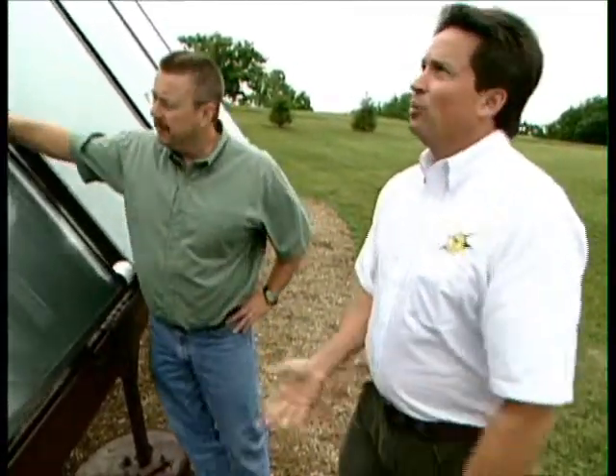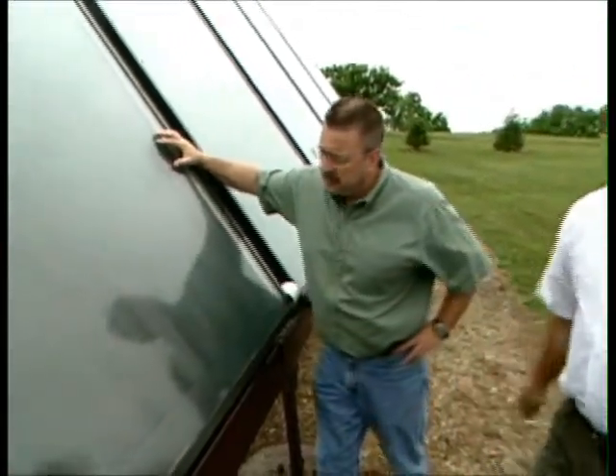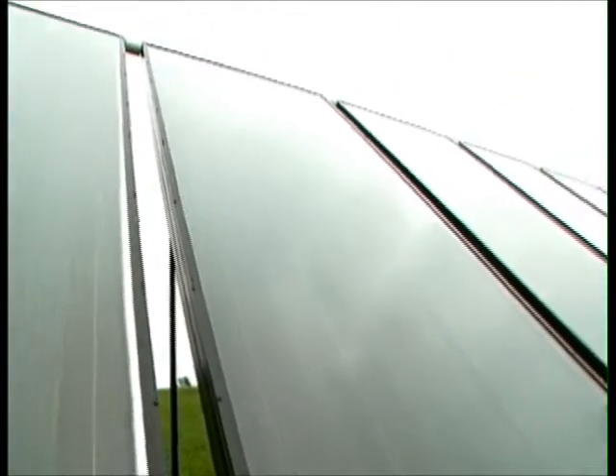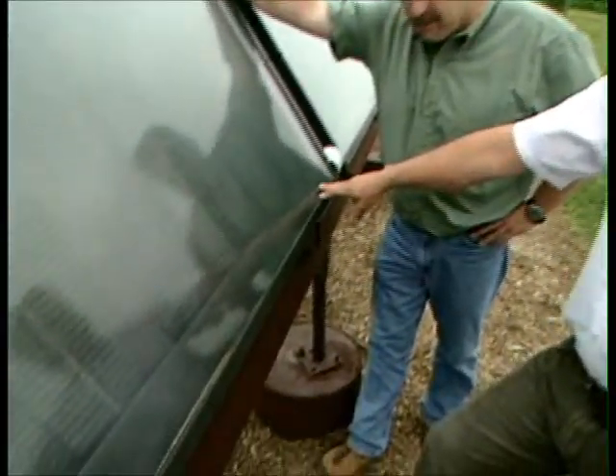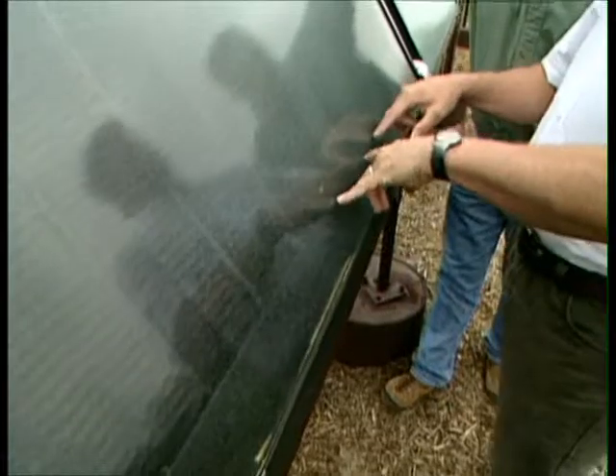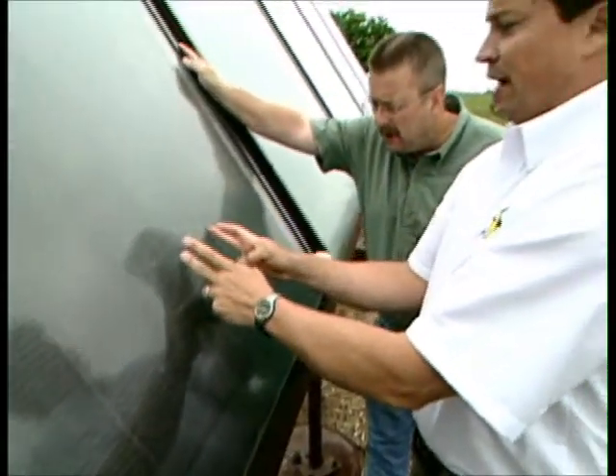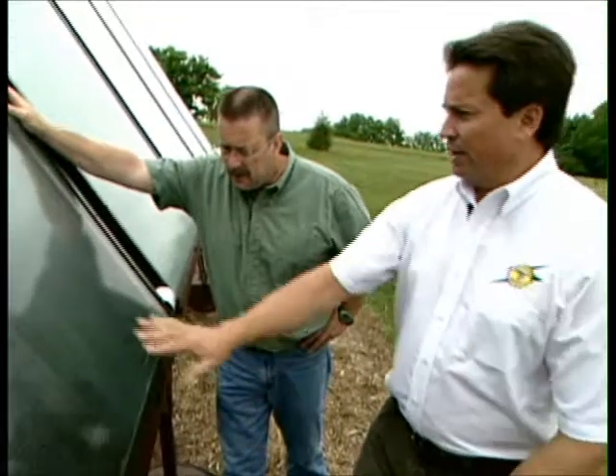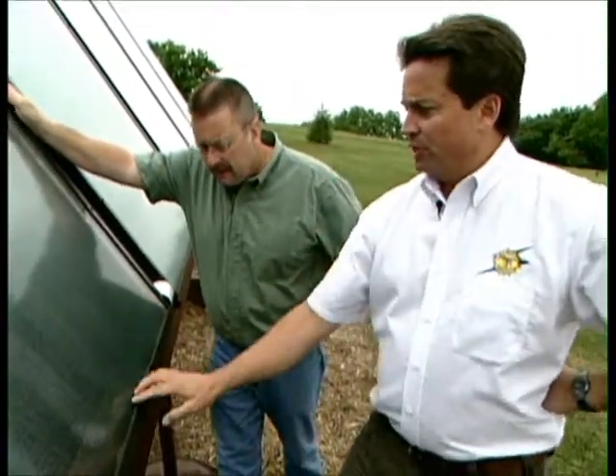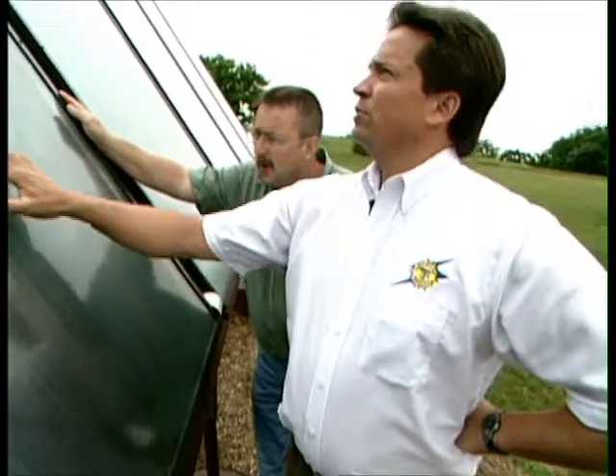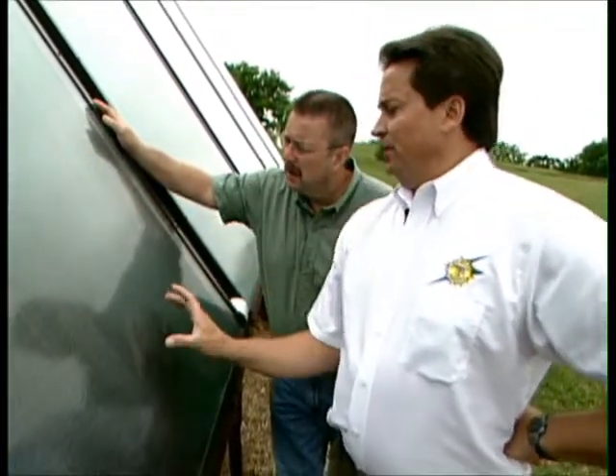Sure, we have 10 4x10 solar thermal collectors here that are manufactured in the United States here in Florida, and we like to use American products whenever we can. So as I look inside there, it almost looks similar to a radiator, or there's metal inside there, and those fins are actually heating up? Correct. The manifold pipes in the bottom are of a larger diameter, and then there's multiple small diameter tubes that go up that are welded to a thin copper absorber plate with a black coating on it that absorbs the sun's energy. So as that fluid is pumped up and rises up through these capillary tubes, we'll call them, it gathers the heat energy from the plate and transfers it to the fluid back into the building.